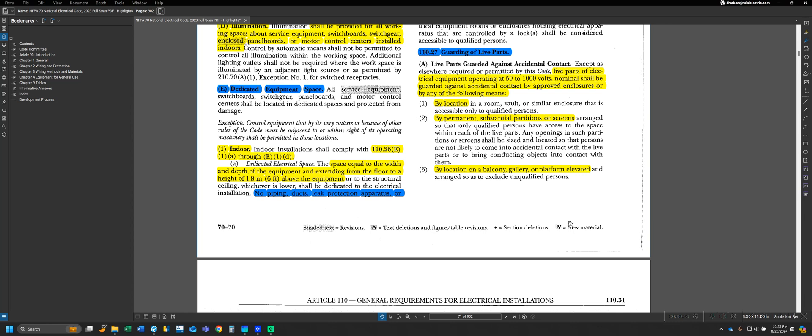This is reflected in our first section here, 110.27 Part A, where it tells us that live parts of electrical equipment operating at 50 to 1,000 volts nominal shall be guarded against accidental contact by approved enclosures or by any of the following means. We either have to have equipment in an enclosure to protect people from touching it, or we have to guard or have it in a specific location where it's accessible.